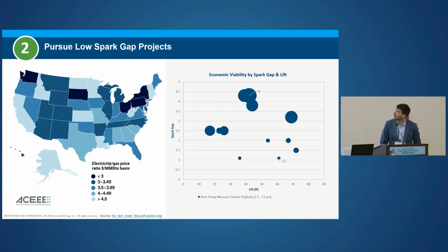Second key takeaway, spark gap is important. This is the ratio of electricity to gas price. In this case, natural gas, but it applies to any thermal fuel. We had some biomass projects as well. So the lower the better here for heat pumps. And as you can see, most of our projects were in the state of Washington, where it is fairly low. But as you can see from the graph on the right, with spark gap on the y-axis, there was quite the range of spark gaps even in Washington.